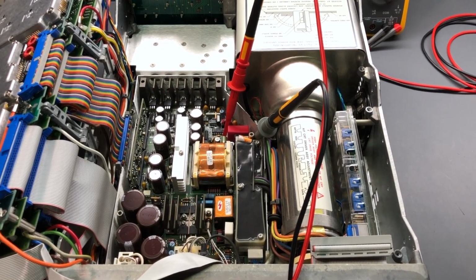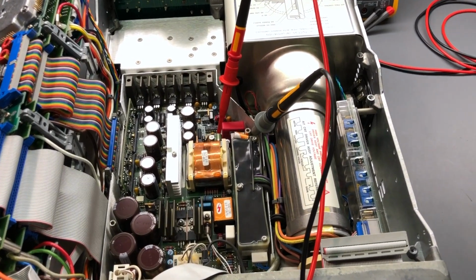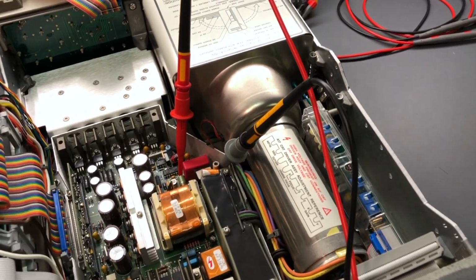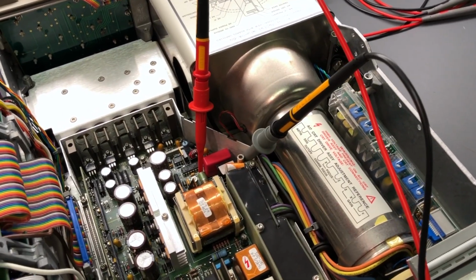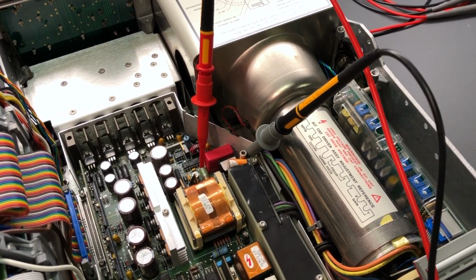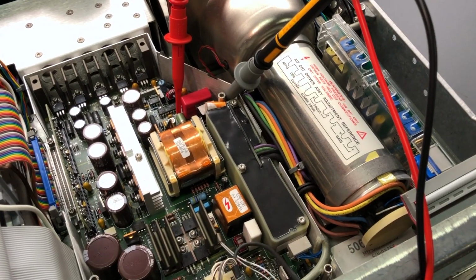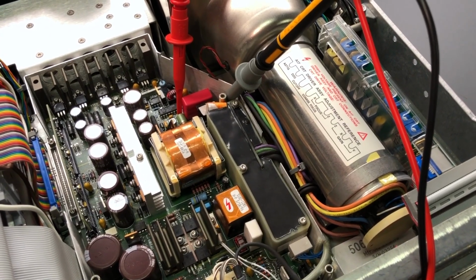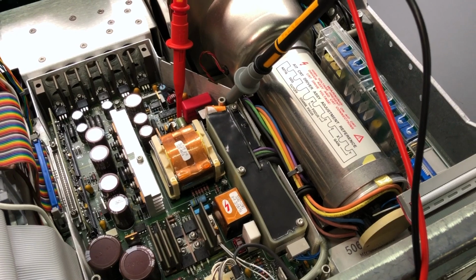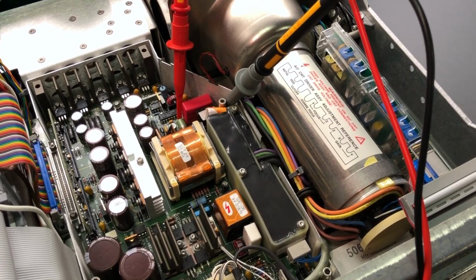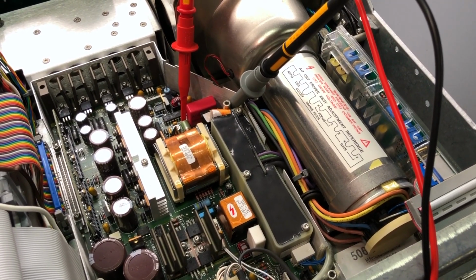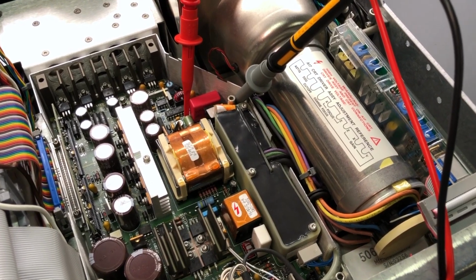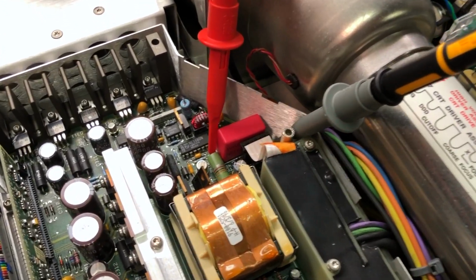Before I put the top cover on the power supply, I wanted to check the voltage at these two test points where you see the probes connected. And the voltage at those test points should be the value that's written on a label on the end of the high voltage module. In this case, the module is marked as 111.5 volts, and that's characterized at the factory. So every module is a little bit different, and the voltage that you set at these test points needs to be exactly what's on that label.